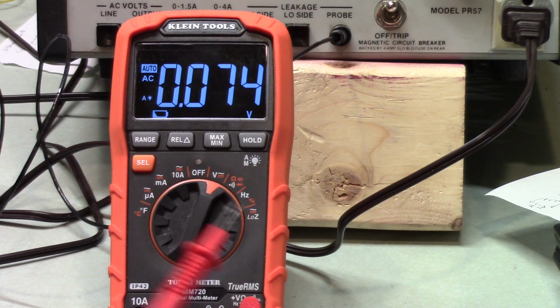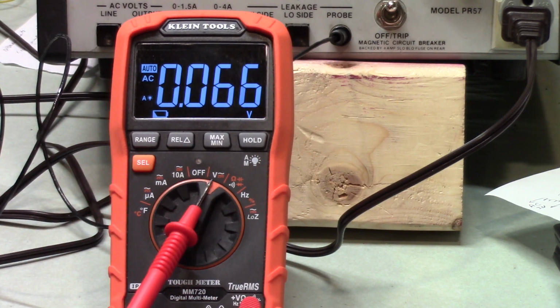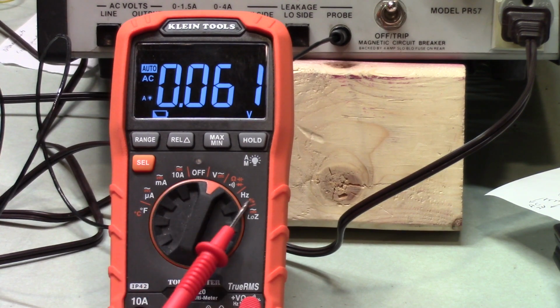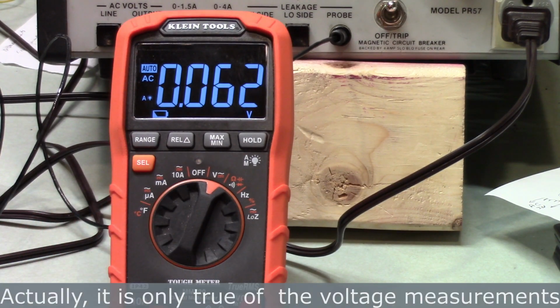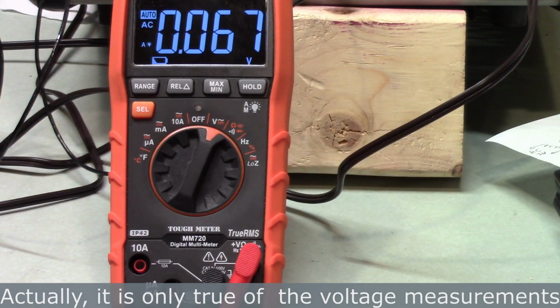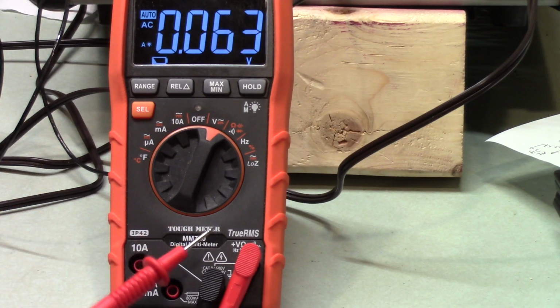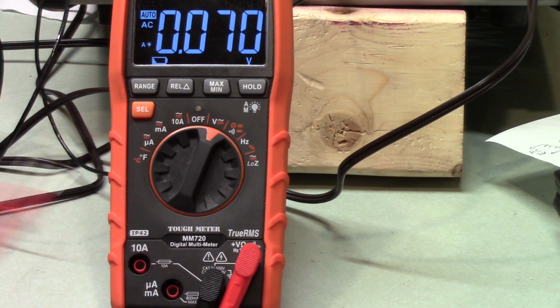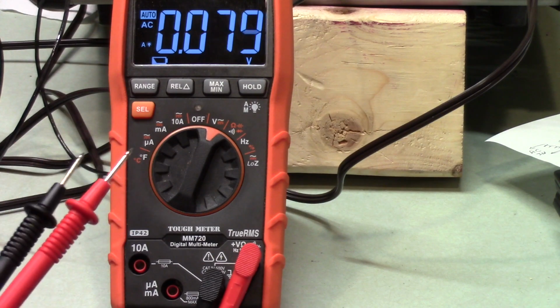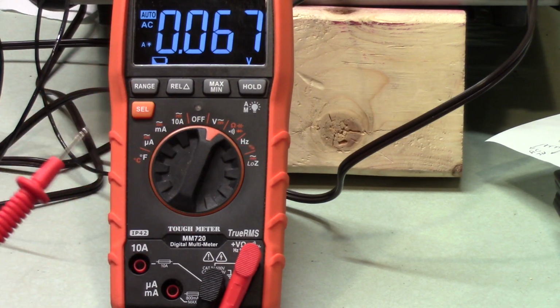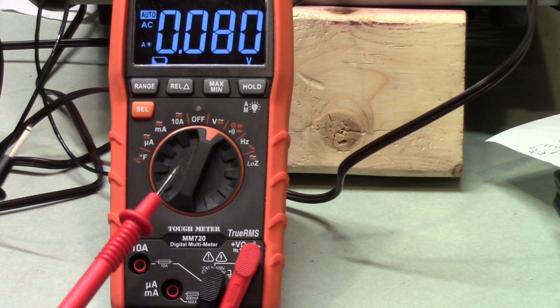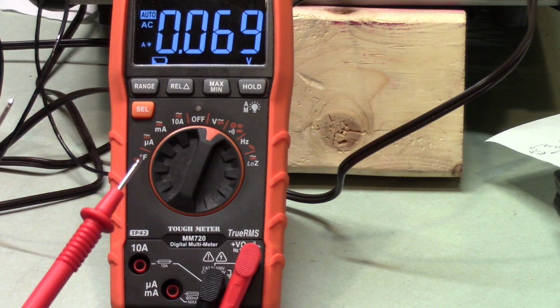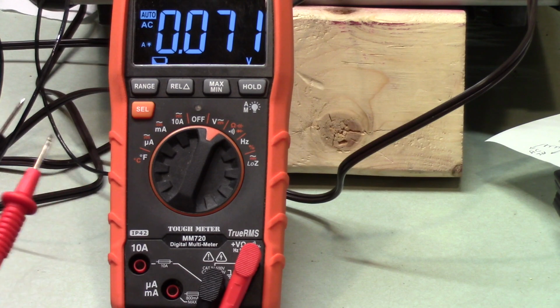It's called low Z. Now, when your meter is set at any one of these other connections, the impedance, the resistance in that meter — and I looked on the meter itself and it doesn't tell me that, but I believe it's 10 megohms of impedance here — so with that much impedance, when you put your meter across a circuit, it's not going to draw the voltage down very much. It's going to be a teeny tiny amount.